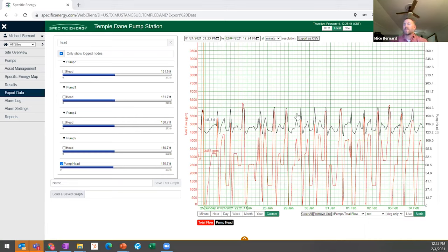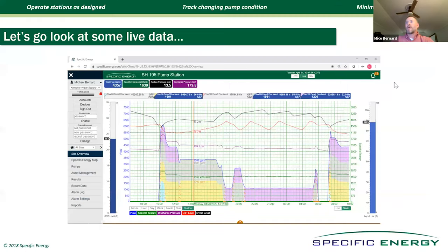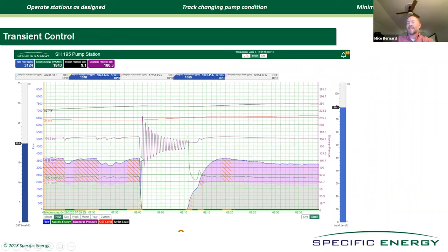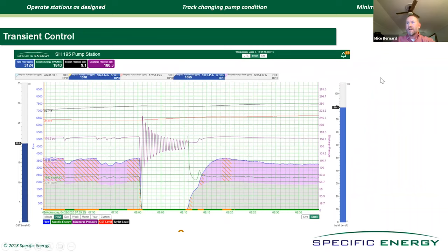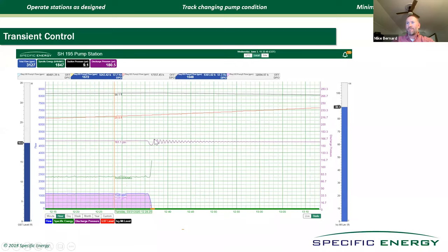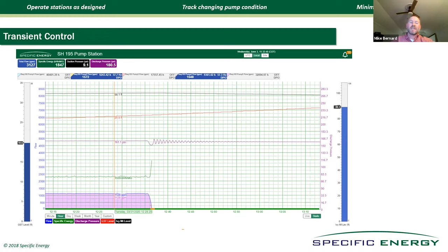Going back to the PowerPoint, I want to show one other thing: transient control. This is a utility in Texas as well that used to be very subject to transients. Here's one in April where they had to take us out of DPO control. You can see the amplitude of this is pretty high. I saw one that went over 250 PSI. They used to have a lot of line breaks in this system before us. This is what it looks like without DPO control. Here's the same pump station with the same x-axis, the same y-axis, and this is what it looks like with DPO control. The amplitude is far smaller. There's still a transient—you can't get away from transients—but you can keep that transient from becoming water hammer that blows lines out of the ground and damages equipment.